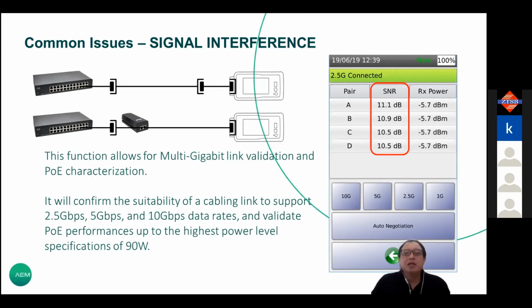So you can see that PoE is not just cable measurement, but you also can measure the noise, measure the power, measure the source, and real time as well, which gives you a very good overview of the practicality when you want to run a PoE system. So those in cabling, those in system lines that provide security systems, provide IoT devices, you can tap on these devices on how to ensure that you get a good measurement when you hand over the system to your client. Whether the cabling is part of your work or not, from this cable measurement, you can determine the cable is able to support the power as well.